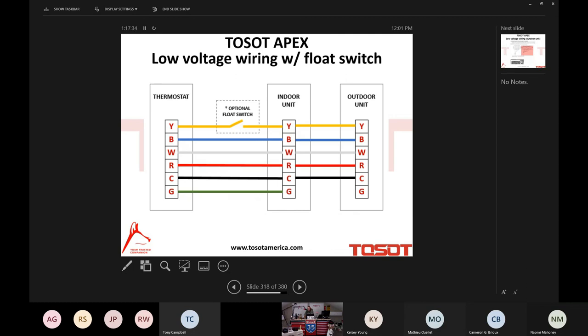Here's another note for you guys, giving you a heads up, take a note. If your customer is going to use an optional aftermarket float switch, it must break the Y terminal. It is more common to break the R. Don't do it. Won't work. Won't stop the system, right? What will stop the system is breaking the Y terminal. So that's something to remember for sure, and something to make sure that your customers are aware of. Aftermarket float switches are necessary by code in many cases, if not all cases, but it has to break the Y terminal.